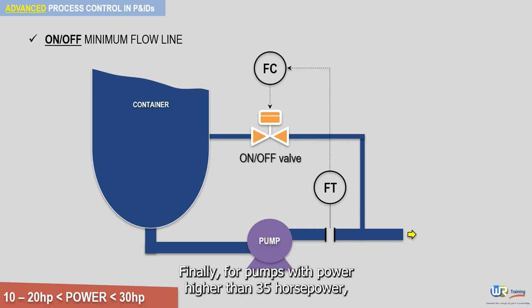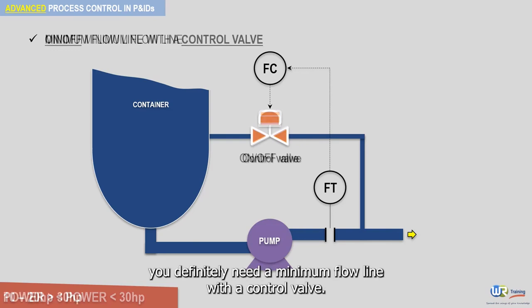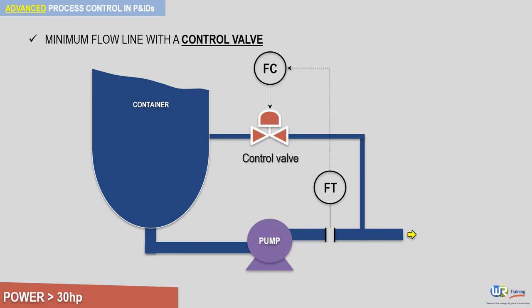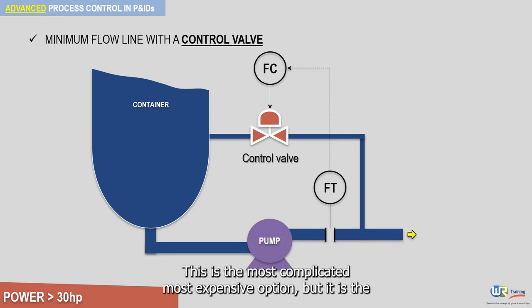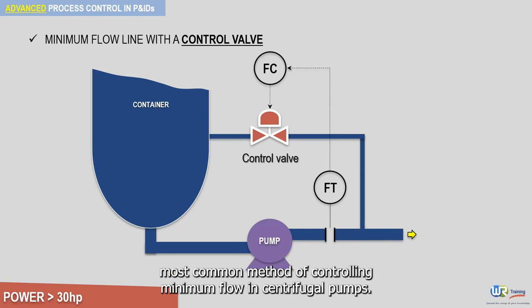Finally, for pumps with power higher than 35 horsepower, you definitely need a minimum flow line with a control valve. This is the most complicated and most expensive option, but it is the most common method of controlling minimum flow in centrifugal pumps.